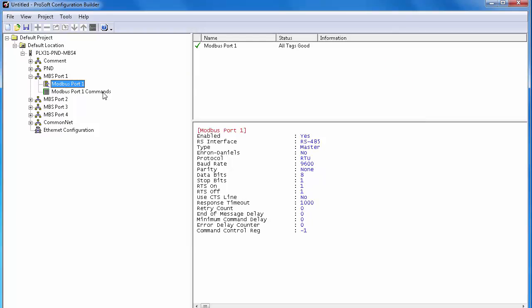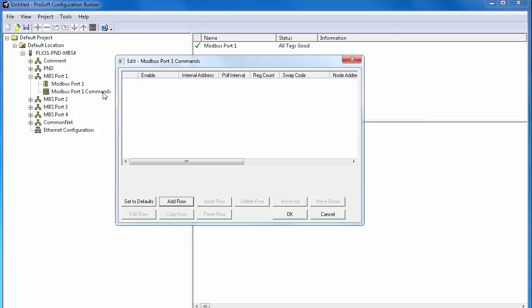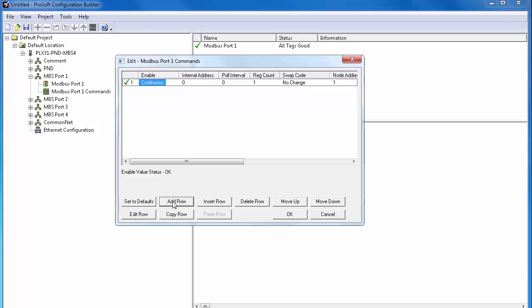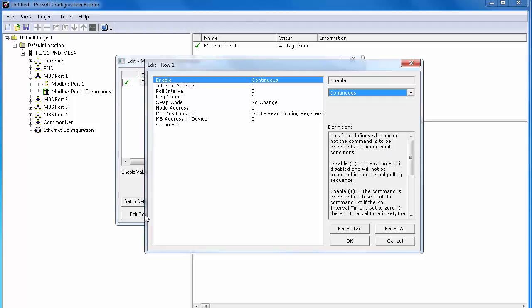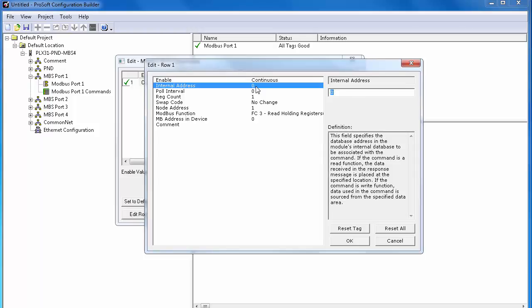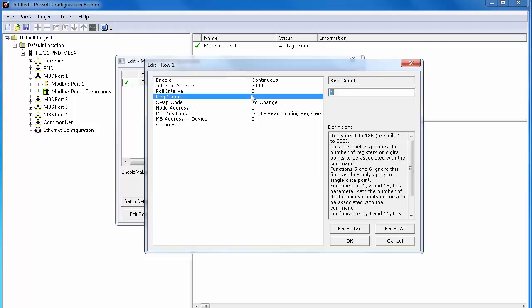Now that the port is configured, we can configure the port 1 command. We'll build one read command and one write command for our master. So add a row and edit the row. We'll begin with the write command. Set enable to continuous because we want the command to poll continuously. Internal address will be 2000, which is the beginning of the write section of our internal database on the Modbus side.